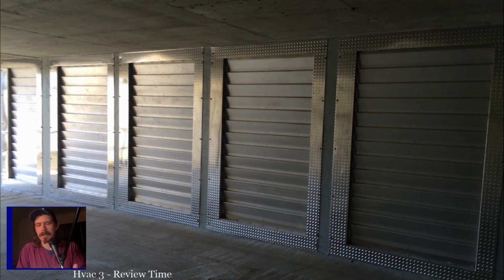But relays, contactors, even motor starters, the only difference between a motor starter and a regular contactor is they'll have some kind of overload on it. But these are all just switches. Time delay relays, it's just a switch that works after a time delay period. Going through compressor short cycle timers, those are compressor contactors. It's basically just another type of time delay relay. Most of the ones we deal with now aren't all mechanical. Most of those short cycle timers are built into boards and things like that.